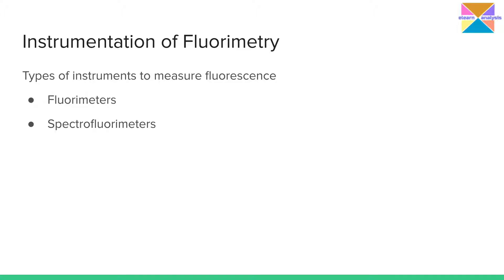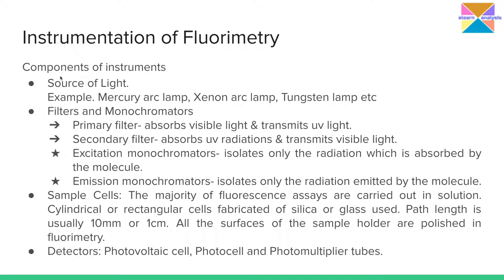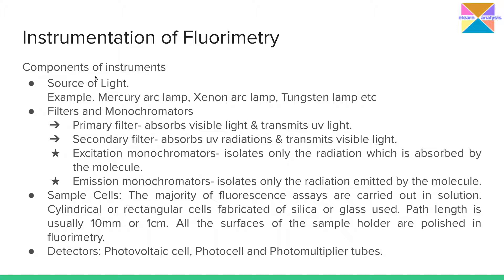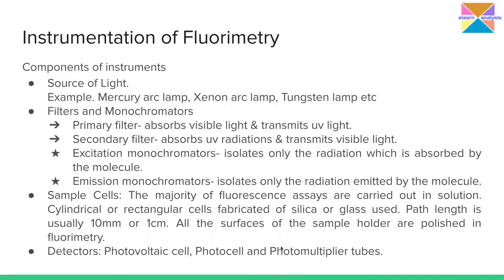Before discussing why two wavelength selectors are used, let me take you through the components of these instruments — the fluorometer and spectrofluorimeter. The first component is the source of radiation or light. The second is the wavelength selectors, which may be filters or monochromators. The third is the sample cell, and the last is the detectors. The sources and detectors are the same as those in UV-visible spectroscopy: mercury arc lamp, xenon arc lamp, tungsten lamp, and detectors such as photovoltaic cell, photocell, and photomultiplier tubes.